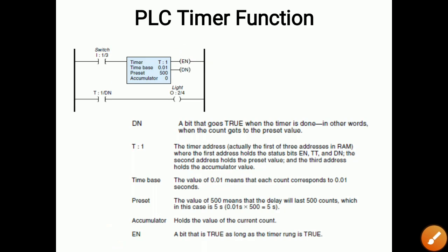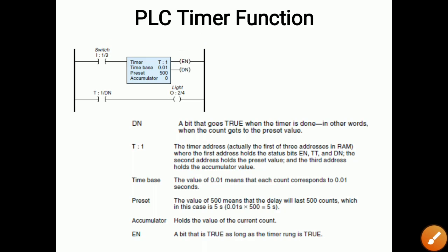The last parameter is EN. EN is a bit that is true as long as the timer rung is true — when this rung is true, EN is also true. So when the timer is on, EN is also on. When the accumulated value is complete, DN gets activated, the DN contact closes, and the light turns on.